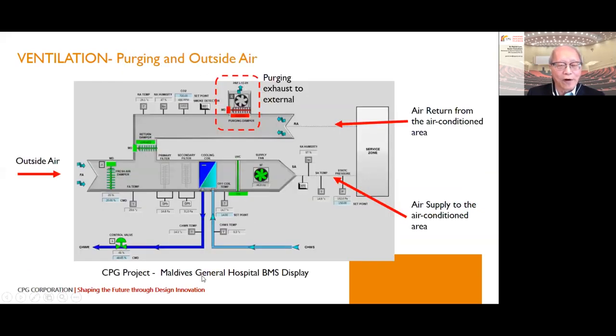This is an example of one of our projects, a hospital project in Maldives. This is the space, for example the office, etc. In the morning before the aircon starts, a purge fan is used to extract the overnight air out of the building and replace it with fresh air. During operation of the aircon, more outdoor air can subsequently be provided to dilute the pollutants.